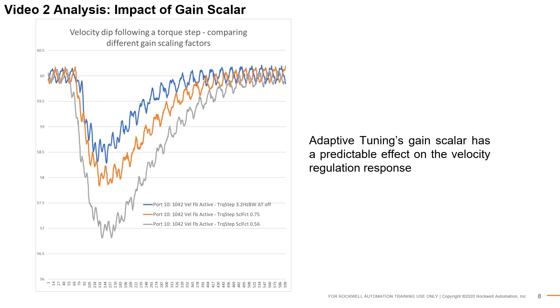Likewise, when the gain scalar continues detuning to 0.5, the effective system bandwidth is further reduced. This is shown by the gray trace. It is observed that the step response changes just like it would if the velocity regulator gains were manually updated. This concludes the gain optimization demonstration.